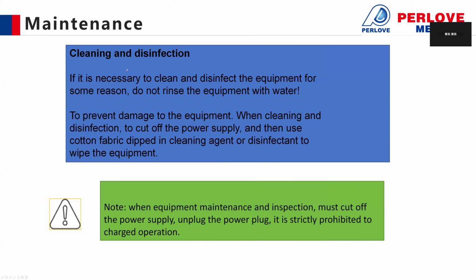Disinfection is also necessary to clean and disinfect the equipment for some reasons. Don't rinse the equipment with water - do not use water. To prevent damage to the machine, when cleaning and disinfecting, cut off the power supply first, then use a cotton cloth dipped in cleaning agent to wipe the equipment. Usually we clean the machine with alcohol, not water. It's very important that if you want to fix our machine, you must cut off the power supply first.